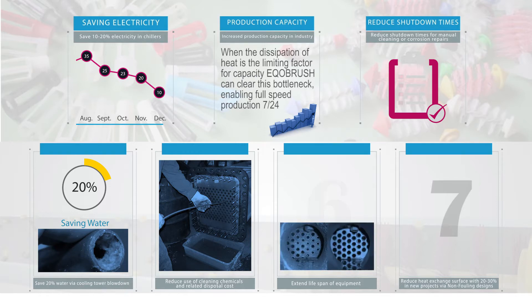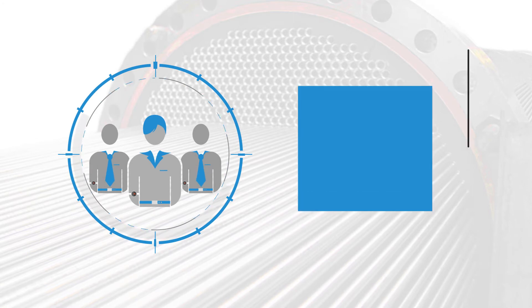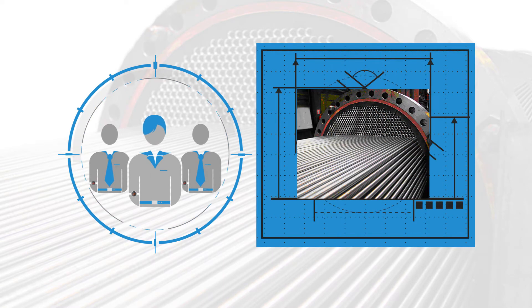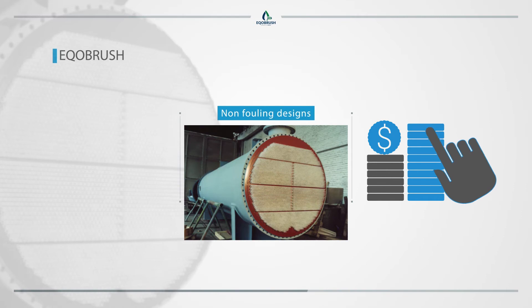Extend lifespan of equipment. Corroded tubes will start leaking and need to be blocked. With increasing numbers of blocked tubes, the equipment eventually can no longer be used. Reduce heat exchange surface by 20 to 30 percent in new projects via non-fouling designs. Design engineers factor in the expected fouling-related efficiency loss by increasing the heat exchange surface. Non-fouling designs are limited in size and CAPEX, therefore freeing up budget for investment in EqoBrush.